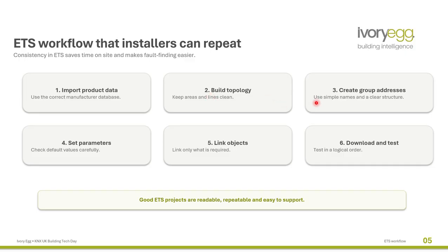Then create the group addresses - as I said, transparent group addresses to be understandable by others. Set the parameters - sometimes you should go through the manual to understand what's happening with a new product, because in KNX most of the time we don't work with one brand, we work with different brands. In this case, you should go to the device manual and understand the parameterization.